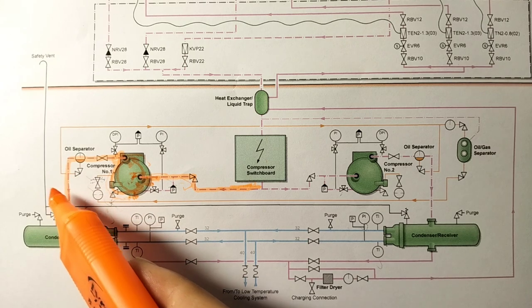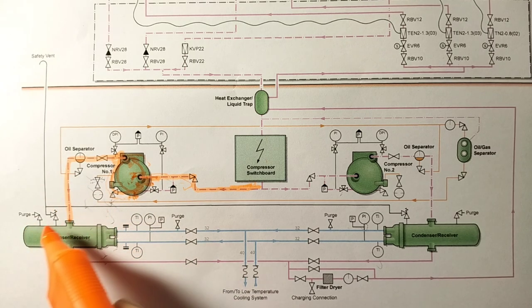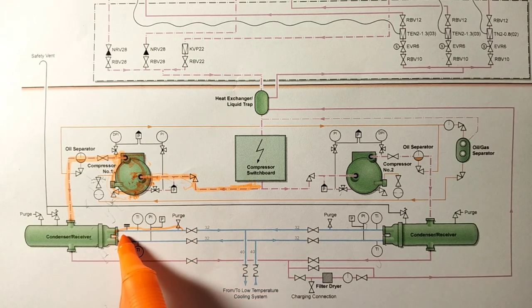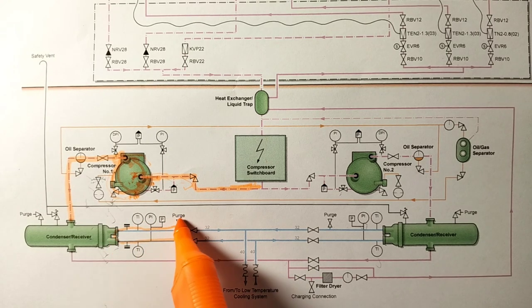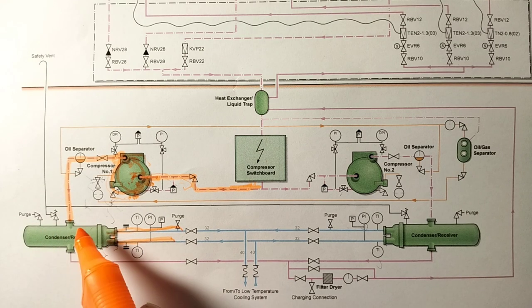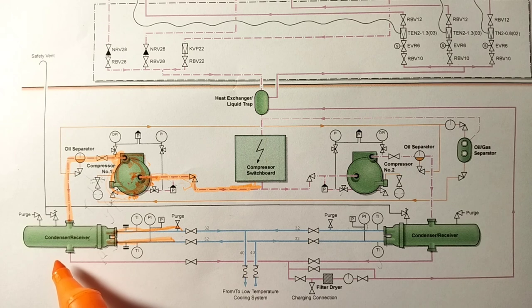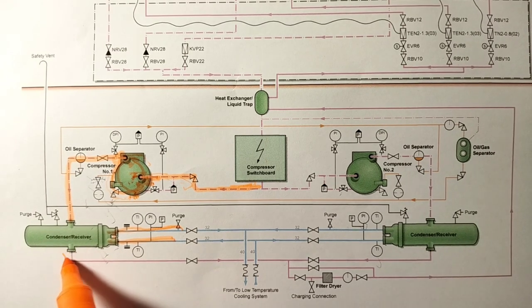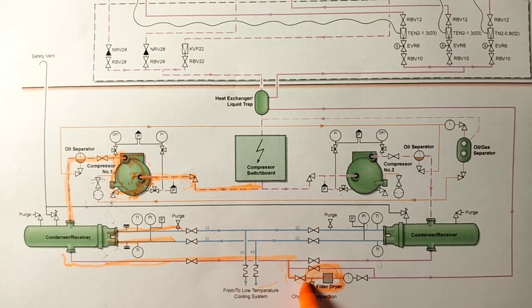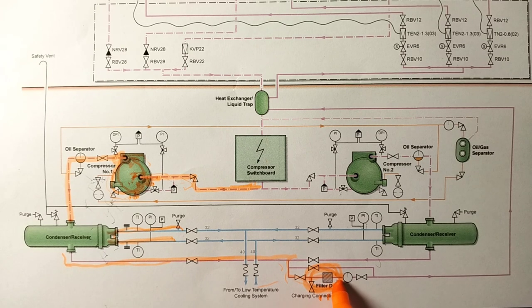This high temperature, high pressure freon enters the condenser for condensation, which is cooled by water circulating from the central cooling fresh water system — this is the inlet and this is the outlet for cooling freon inside this condenser. After this process, the gas is condensed inside the condenser to become a liquid. Then this pressurized liquid refrigerant passes through the line and through the filter dryer, which absorbs moisture present in the liquid freon.